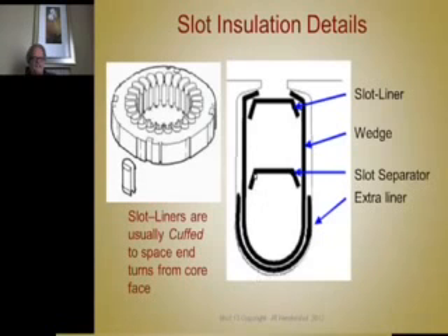This is a slot separator. If you have one side of a coil of phase A in here and you have phase B there, this is a slot separator that insulates the two phases from each other, because you might have plus 600 volts here and minus 600 volts here, or something pretty close to that. So you have a big potential difference across any adjacent conductors that would be touching without this slot liner. And this is a top stick or a slot wedge that goes in the top.